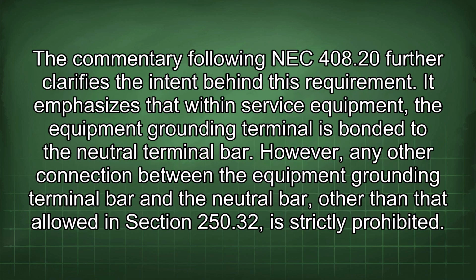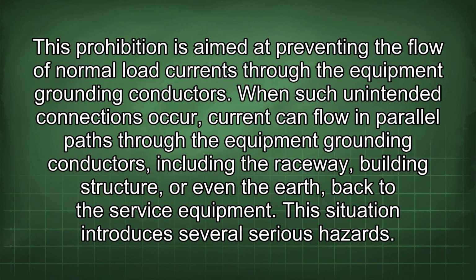The commentary following NEC 408.20 further clarifies the intent behind this requirement. It emphasizes that within service equipment, the equipment grounding terminal is bonded to the neutral terminal bar. However, any other connection between the equipment grounding terminal bar and the neutral bar, other than that allowed in Section 250.32, is strictly prohibited. This prohibition is aimed at preventing the flow of normal load currents through the equipment grounding conductors. When such unintended connections occur, current can flow in parallel paths through the equipment grounding conductors, including the raceway, building structure, or even the earth, back to the service equipment.